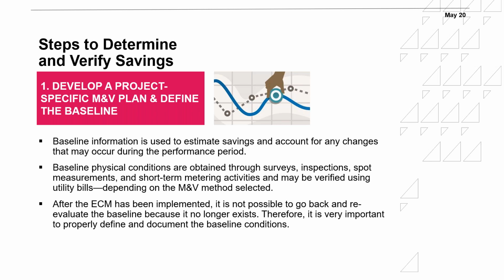After the ECM has been implemented, it's really not possible to go back and reevaluate the baseline because it no longer exists. We cannot really go back. If we change the chiller, we cannot go back and take measurements on the old chillers because it's gone. It's not possible anymore. So it's very important to properly define and document the baseline conditions, which is normally done during the investment grade audit. It needs to be very detailed so you know exactly what was happening during the baseline period.